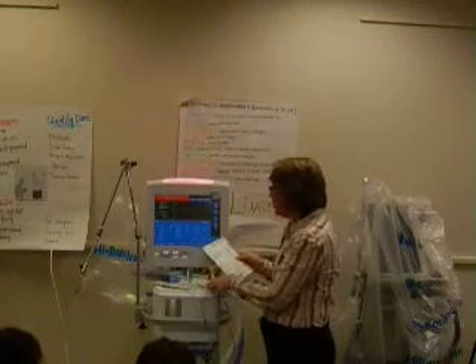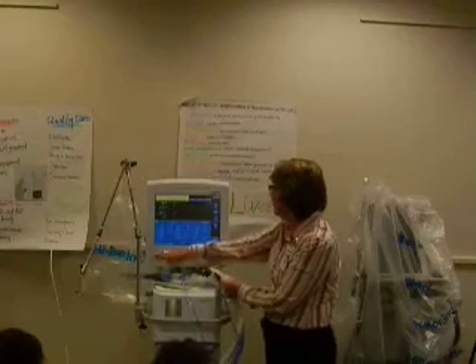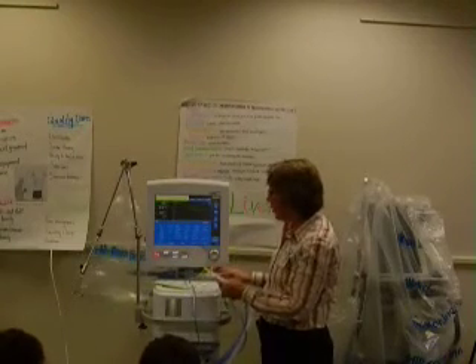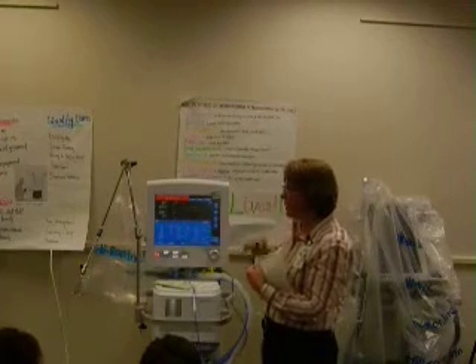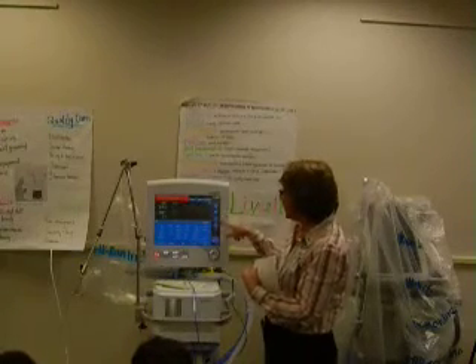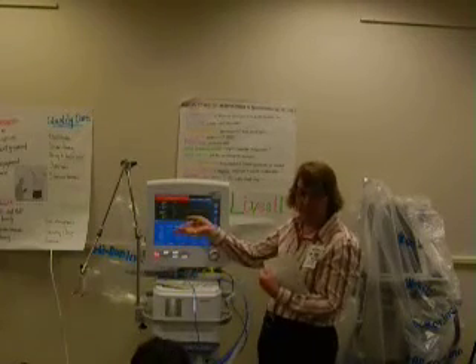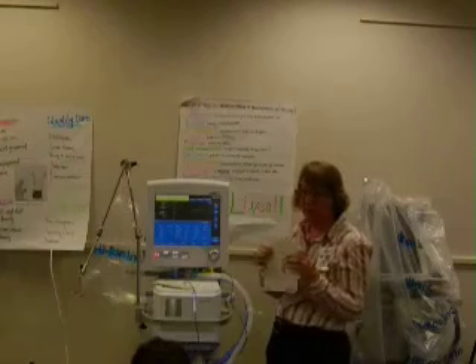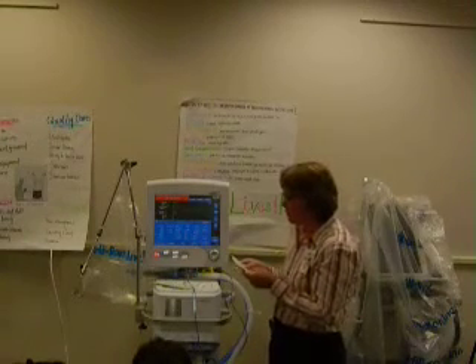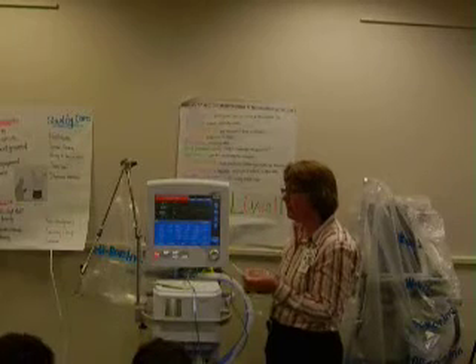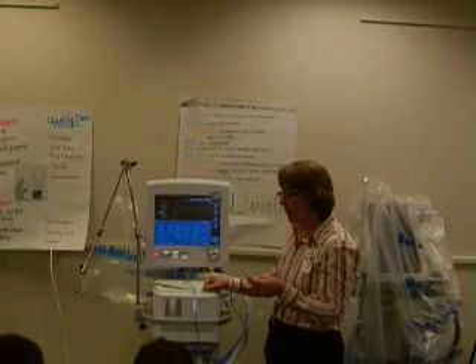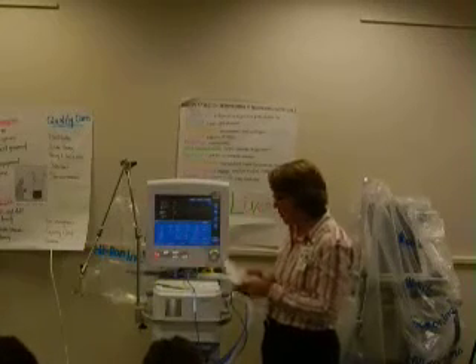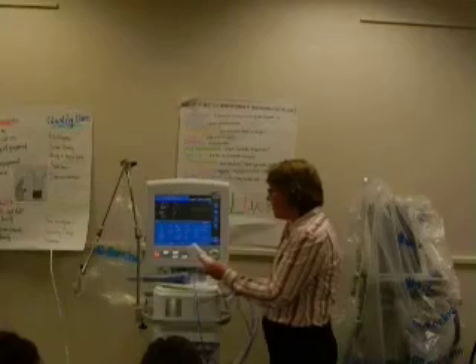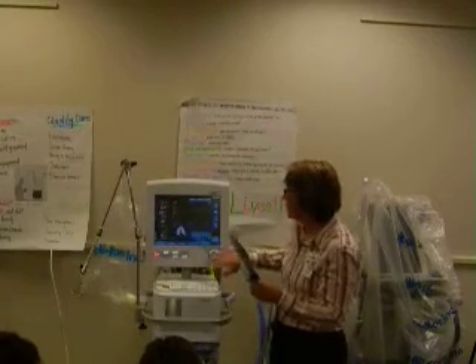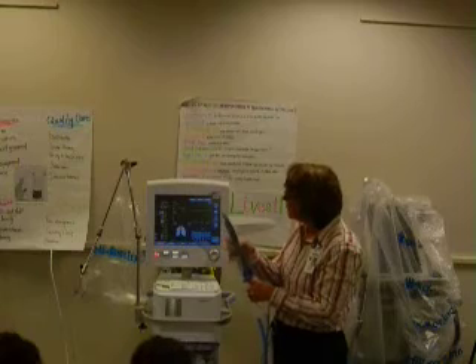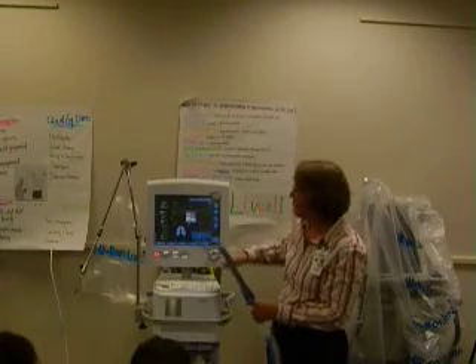And after a minute or so, what you have to do is turn the card over and make sure that the values that are here match what's in the back here, because it's making sure of the default settings. We have a rate of 15, we want to be getting our rate of 15 at a volume of 500. So it tells you the range it wants your readings to be within. What if they're not? You have to send it back to Biomed. But you give it a minute or two, it takes a minute to get to where you want it to be. So we're going to pretend we did all that. Squeeze the demonstration lung a couple times. You're supposed to get that little triangle. See that little thing?